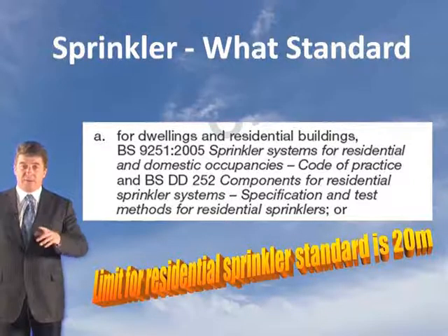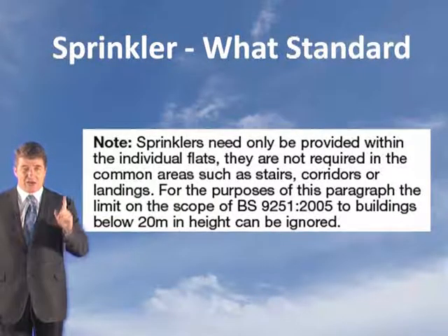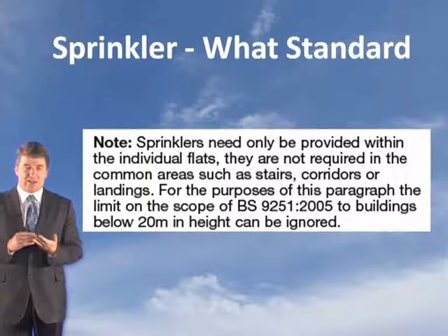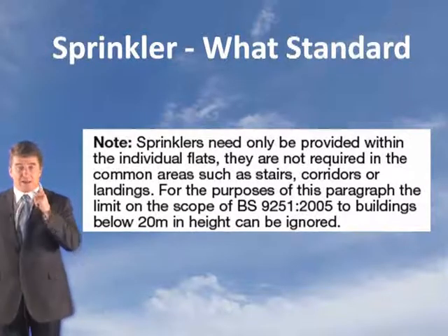However, Approved Document B says that sprinklers need only be provided within the individual flats. They are not required in the common areas such as the stairs, the corridors or the landings. What they're saying is these should be sterile areas anyway. They're not the risk areas. And this is a very important statement.